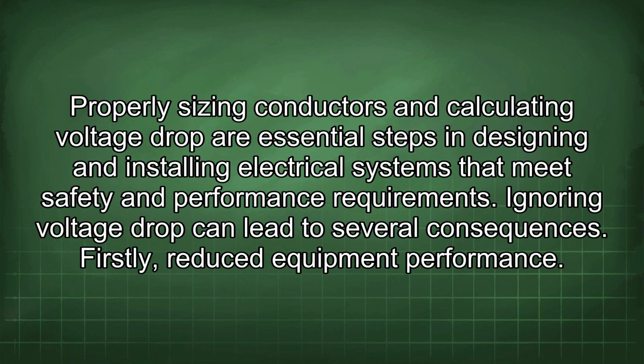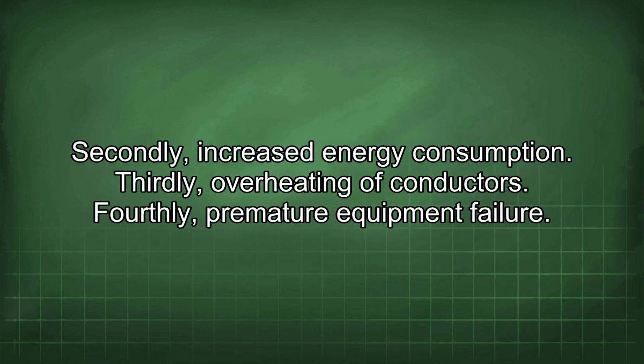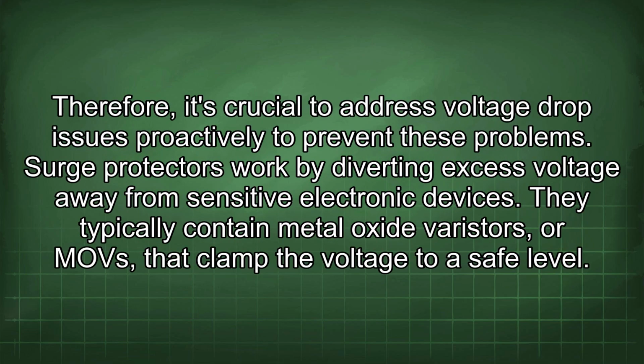Properly sizing conductors and calculating voltage drop are essential steps in designing and installing electrical systems that meet safety and performance requirements. Ignoring voltage drop can lead to several consequences. Firstly, reduced equipment performance. Secondly, increased energy consumption. Thirdly, overheating of conductors. Fourthly, premature equipment failure. Therefore, it's crucial to address voltage drop issues proactively to prevent these problems.